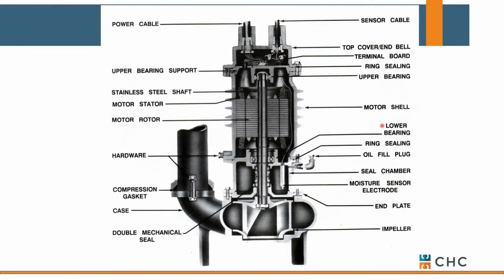What's that doing for us? There are a few unique things when you stick a pump under a body of water that you need to protect for. A standard commercial motor is air filled, meaning there's no hydraulic oil in there. It's simply a motor encased in air, if you will. Obviously, we want that watertight. So you tend to have electrical connections, maybe a temperature probe and a moisture probe. All that gets epoxied at the factory.